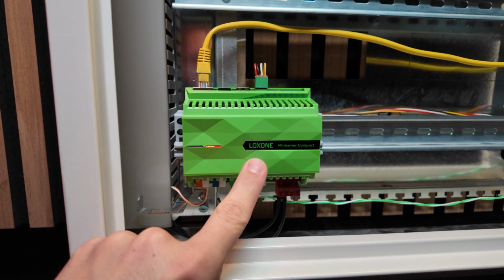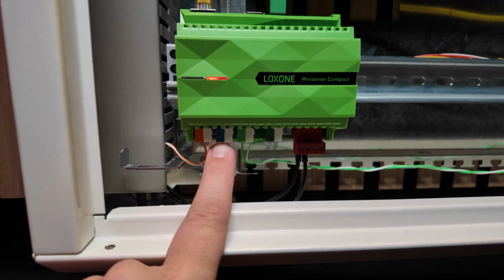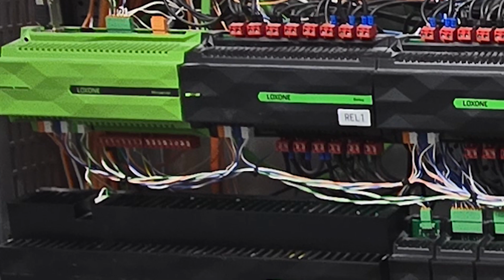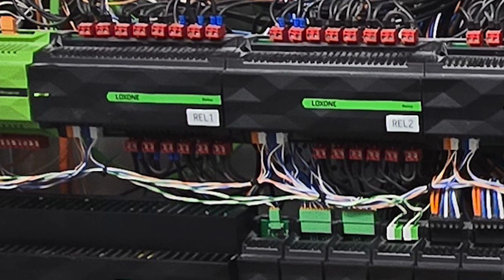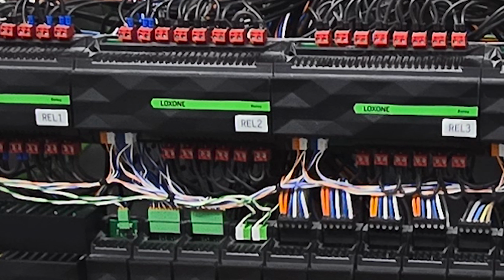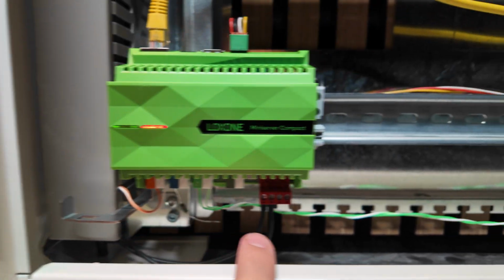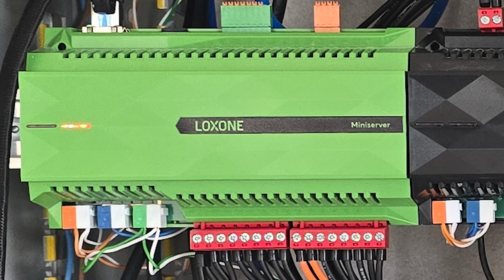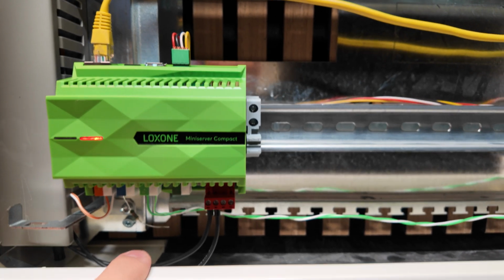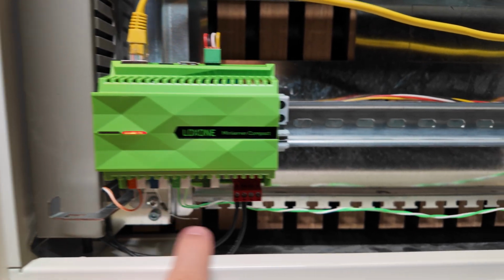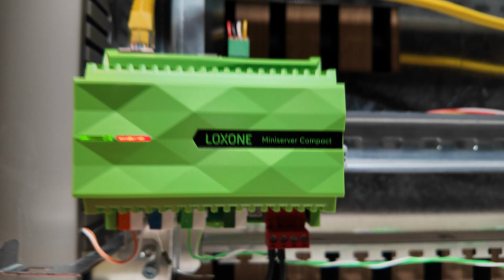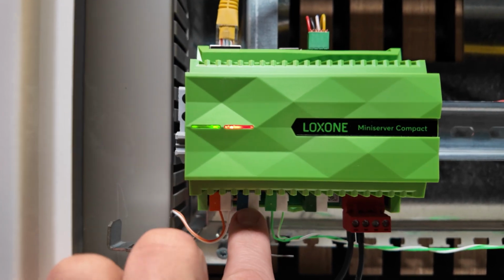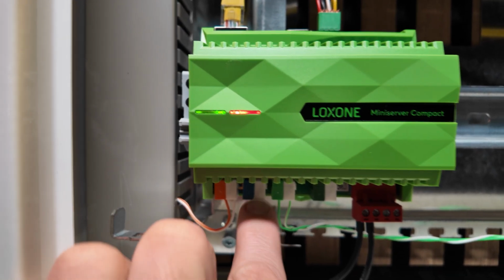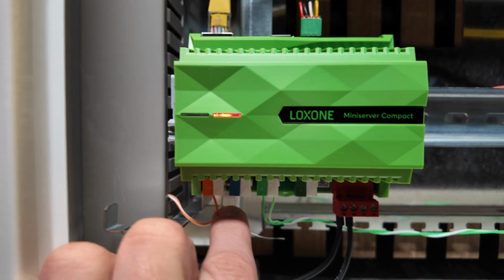Now that the Miniserver is up and running, we could expand the system with extension modules, let's say a relay extension. Then I typically just go from the plus and the Link with two twisted pair cables to the next extension. What is super important here is to always go in a line like this. The first thing I always check is how many cables are connected to the blue clamp on the Miniserver, which can only be one cable.